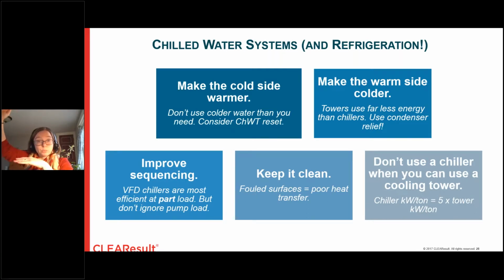So if you make your chilled water a little less aggressively cold, your lift goes down. If you help your chiller reject heat a little better, whether that's by keeping the air fins cleaner or whether it's by running your tower a little harder, you reduce lift. So that's a really, really good thing to remember generally for towers and refrigeration. Keep a good eye on sequencing too. It's a little hard to think about how to sequence VFD chillers if you're used to sequencing constant speed chillers.